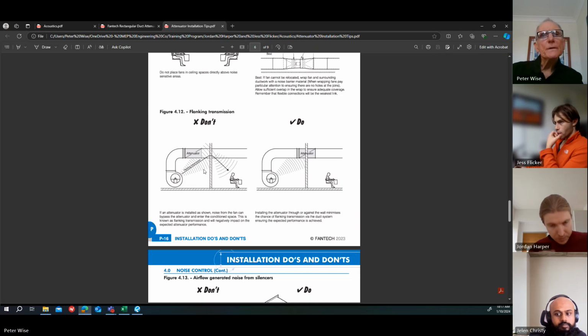Quite often you'll see they're showing a centrifugal fan in a plant room here. That might be an air handling unit, for instance, or it might be a fan. If you need an attenuator, it's better to put it through that wall, if you can do that. If that's a fire rated wall, that makes it very difficult. But if it's not a fire rated wall, if you can put the attenuator through the wall, then you're not only attenuating the noise from the source, from the fan, but you're stopping the breakout noise from the fan breaking out through the plant room wall, which is what's shown on this.